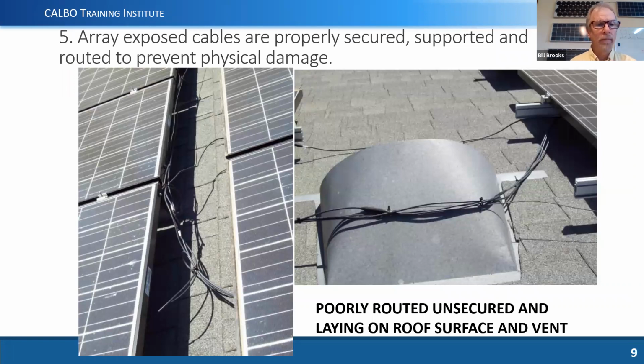Okay. The array exposed cables are properly secured and supported to prevent physical damage. Here we see some poorly routed cables, some of them hung on the ground wire, just hanging around. It'd be a trip hazard if you're trying to walk around on the roof. I see it again here. I like to call this the attic ventilator support system, which is not a support system, or the comp shingle roof support system, where the wire is just laying on the roof.